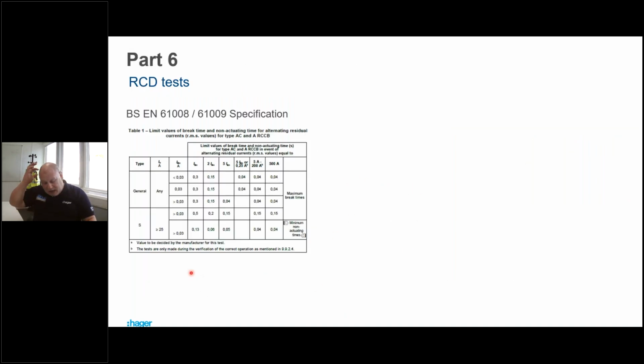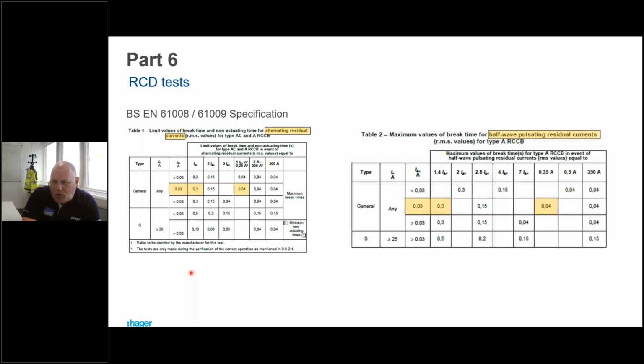RCD testing. As I mentioned earlier, 2 years ago, RCDs were thrown on their head when we brought out all these other devices. Type AC was the standard. We've got type A, type F, type B. Testing totally changed. We were looking at testing all these devices depending on their type. It made people go out and buy new test equipment, as their old test equipment possibly didn't have the settings they needed.